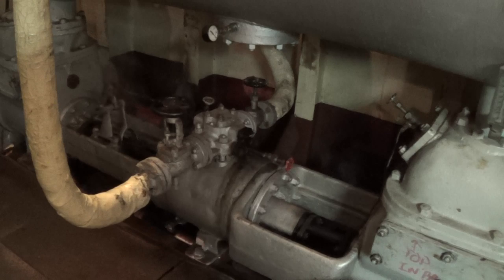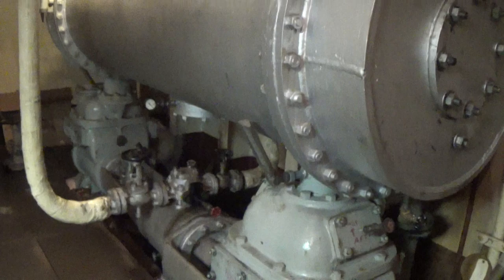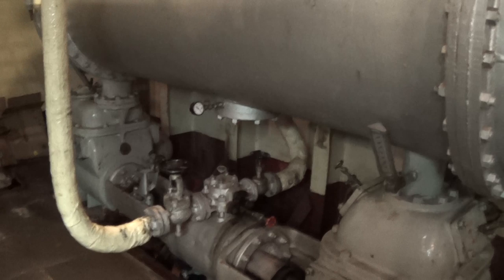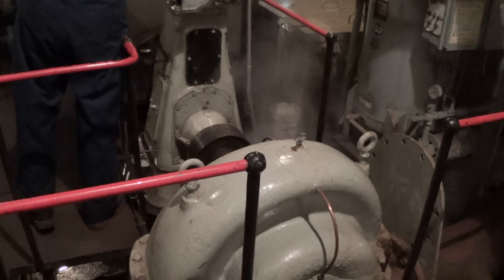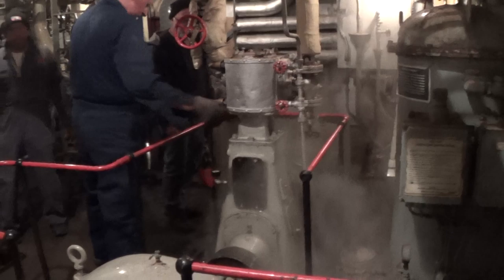This is the auxiliary condensate pump. It takes steam from the auxiliary system, runs it past seawater, and turns it back into condensate, sending it to the feed and filter tank. We use this as a condenser when we're not running the main engine and have to turn steam from the auxiliary pumps and motors back into condensate to put into the boiler. Jack is starting up the main condenser pump.